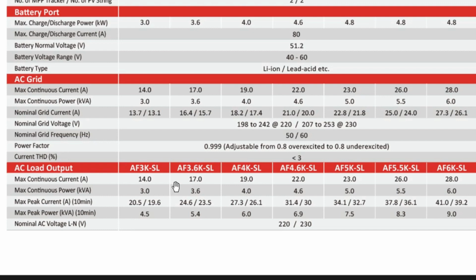These two types of load have completely different characteristics. For example, if the loads have a motor inside, especially during the very start period, this kind of load will need more current than the normal rated current. This should be considered, so we also give a suggestion for this peak current in amps, and during this peak current, the inverter can support continuous operation for 10 minutes.